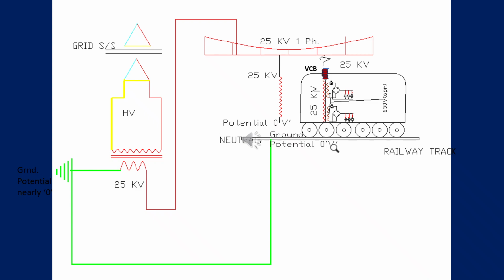From the overhead system, the pantograph is collecting the current. There is a vacuum circuit breaker. If you close it, then the power supply will go to the main winding of a transformer inside the locomotive. From the loco, it is getting 25 kV, but another end is at neutral voltage. That means it is connected with the ground with the help of the loco body, wheel and track to the traction substation grounding point. So the track is working as neutral or ground.